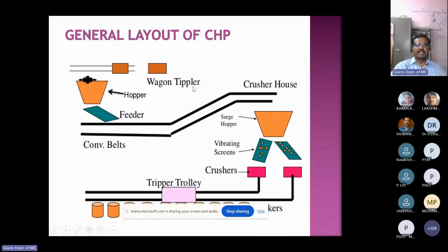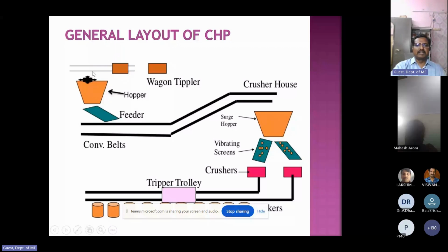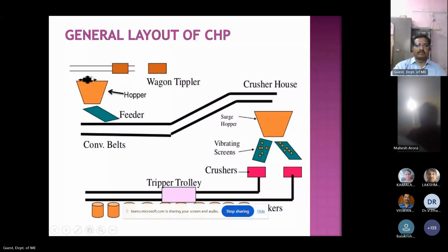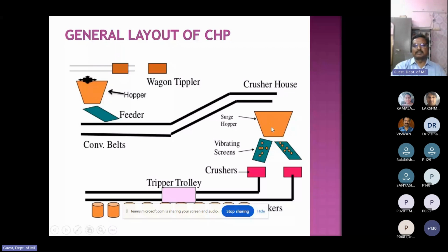This is the main general layout of a coal handling plant. Here, wagon tipplers come and unload into the hopper. So these come to the conveyors. These are all belt conveyors. These belt conveyors send the coal to the crusher, where it is crushed into 20 mm size. These are the vibrating screens. That means if any particle less than 20 mm size is there, those particles are directly bypassed and sent to the belt conveyor. After crushing, these are sent to the bunker.